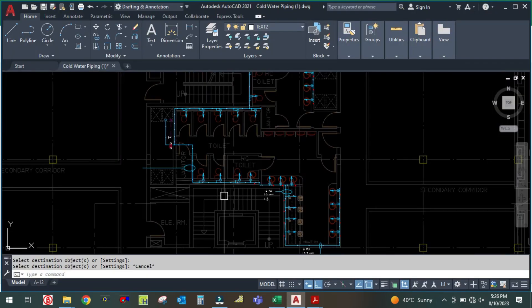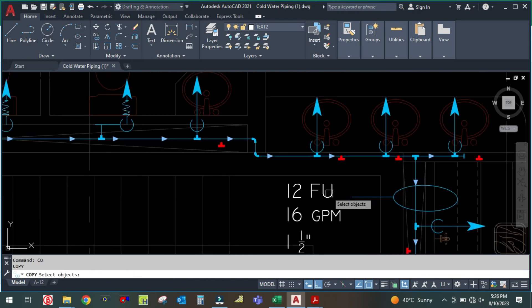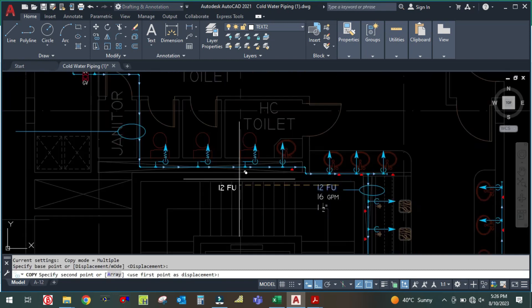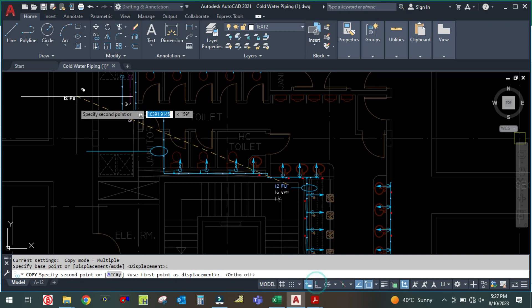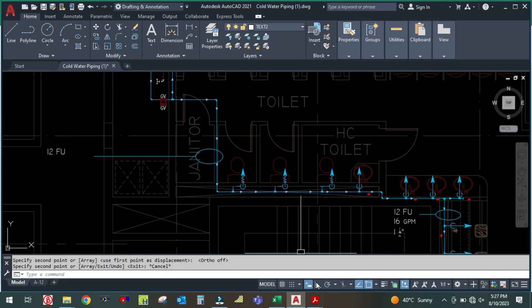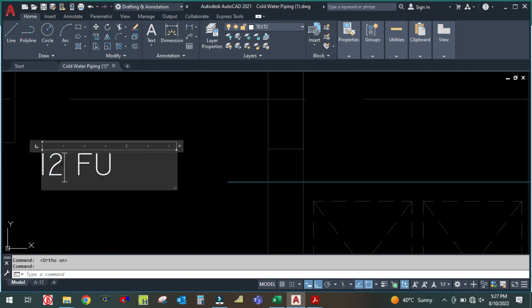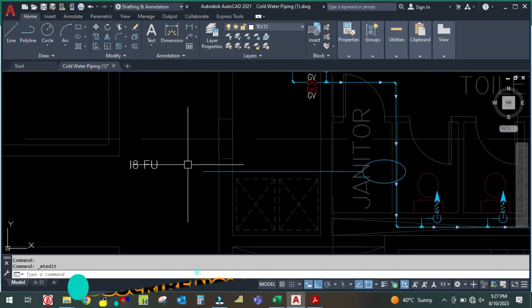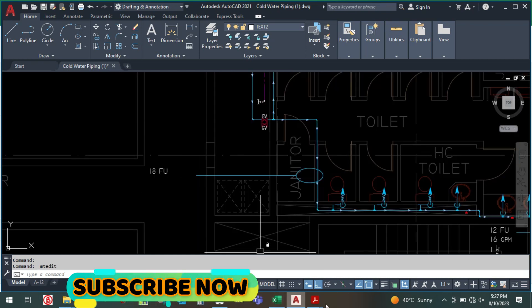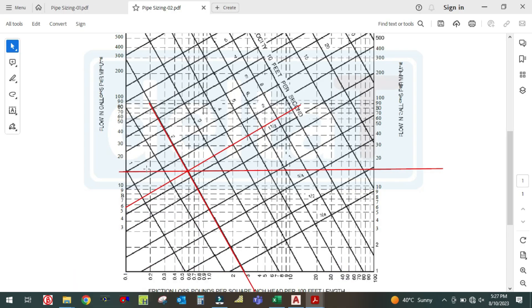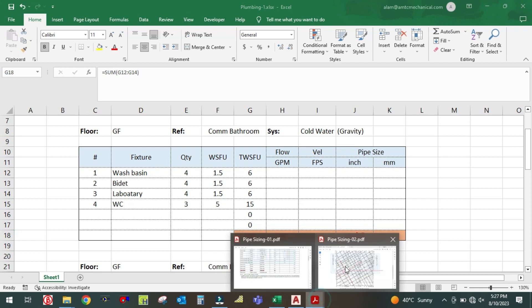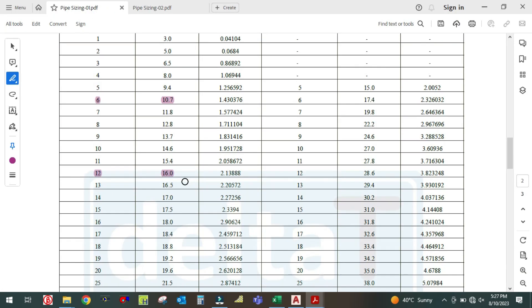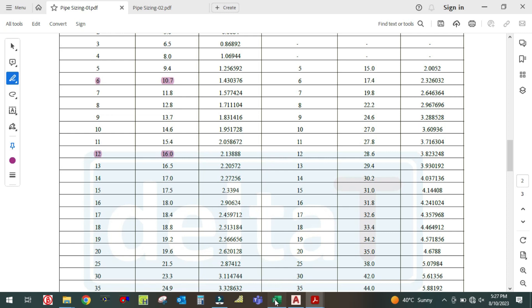So the total fixture unit adds up to 18. For 18 fixture units, check the demand table: 18 fixture units gives a GPM of 18.8.